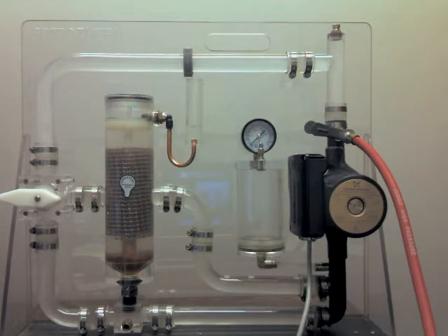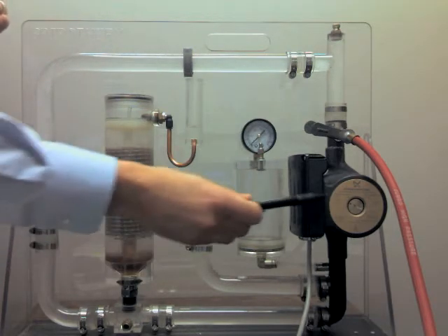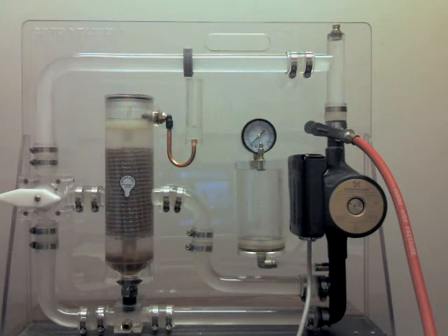But when I put some air here, the first thing that you hear is the pump cavitating. So first and foremost, you want to get all the air out just to protect your equipment. Pump seals and bearings will break down, yes, but our customers say, hey, I'm having to replace these things a lot sooner than I should, and when we investigate, usually air is a big factor in that. It just shortens the life of them.